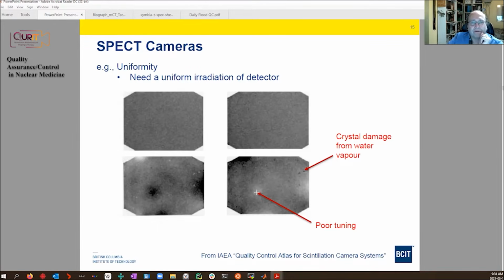These white spots, usually you see that here we have a higher count density than the surrounding areas. That could be caused by poor tuning. If we had tuned the camera and this was still there, that can be some deeper problem. If you just bought the camera and you see these little dots here, you would want to send it back. That means the crystal, which is supposed to be hermetically sealed, if the seal wasn't good and water vapor in the atmosphere leaked in, the interaction between water vapor and a salt crystal essentially can cause these little pock marks, and that's not acceptable. It's going to adversely affect the performance.